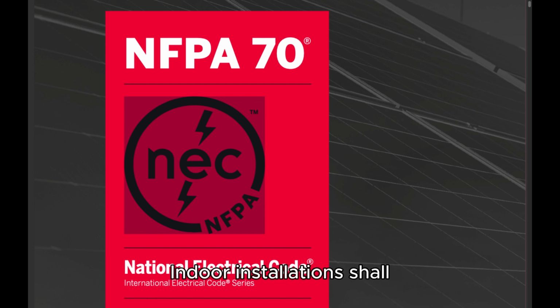1. Indoor. Indoor installations shall comply with 110.26(E)(1)(a) through (E)(1)(d). A. Dedicated electrical space. The space equal to the width and depth of the equipment, and extending from the floor to a height of 1.8 meters (6 feet) above the equipment or to the structural ceiling, whichever is lower, shall be dedicated to the electrical installation. No piping, ducts, leak protection apparatus, or other equipment foreign to the electrical installation shall be located in this zone. Exception: Suspended ceilings with removable panels shall be permitted within the 1.8 m (6 ft) zone.